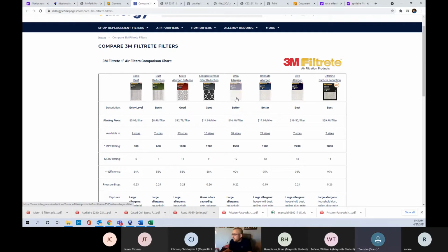No. 3 months. Yeah, 3 months. And it just won't hold up. It gets stopped up with stuff because it catches everything. They're good at doing what they do, but they're too good because they stop everything, including the air. So these are harder on your motors. You don't get the design airflow that you're supposed to be getting. So now your air conditioner is starving for air. So that causes all the problems that can cause. And then over time, this causes your motor to have to work harder, which causes early failure in blower motors and stuff like that. So I hate good 1-inch filters.